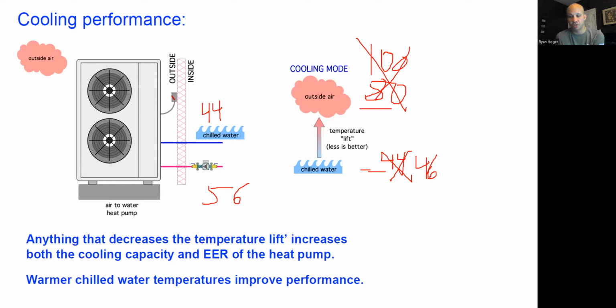I can't go that extreme with the chilled water, because in most applications, nearly all, the chilled water coil's job is also to dehumidify the air, not just cool it. So while I could send 60, 65-degree water into the coil and cool the air down, with 65-degree water I'm not going to be able to hit the dew point of the air and hence dehumidify the air. So that's not going to work for most projects. So I can bump it up a little from 44 to, like in this example, 46, but I can't be too insane with it. So that's a heat pump chiller.